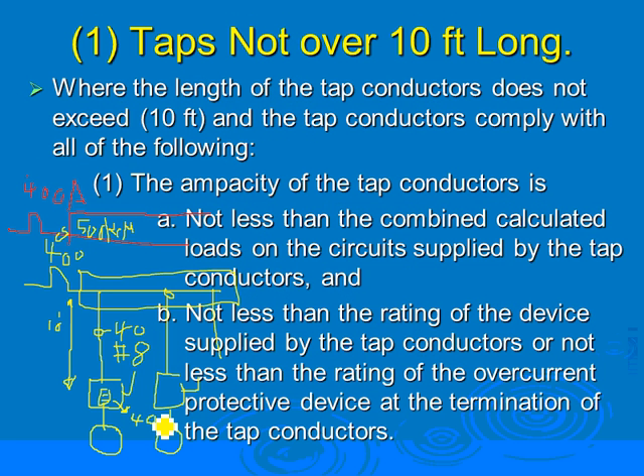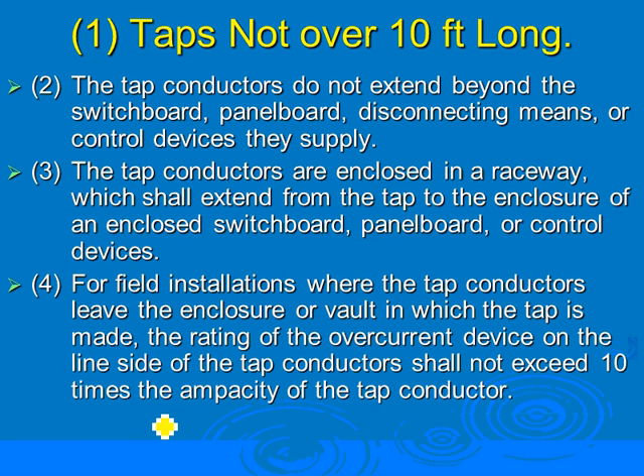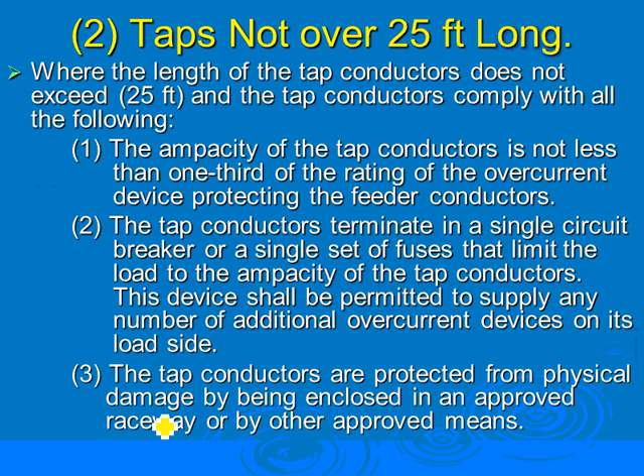So if you look at the ampacity of the tap conductor, it is not less than the combined calculated load on the circuit supplied by the tap, not less than the rating of the device supplied by the tap, and so forth. That's what we get. And if you go outside and wire it in the field, this is where the 10 times came to be. Any comments, guys? Anybody's excited about this rule? No? What's the article on?